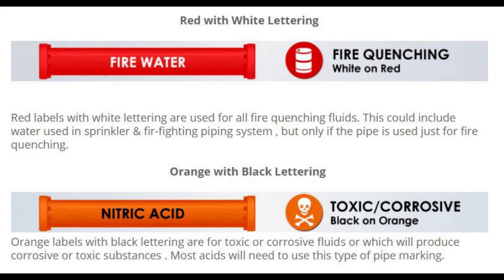Orange with black lettering: Orange labels with black lettering are for toxic or corrosive fluids, or fluids which will produce corrosive or toxic substances. Most acids will need to use this type of pipe marking.